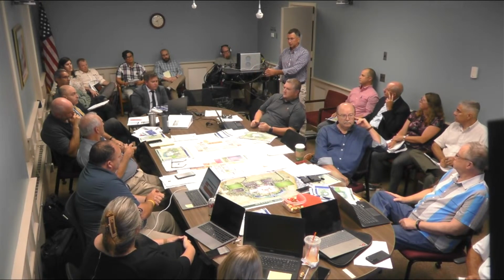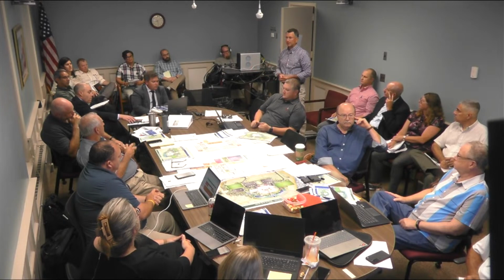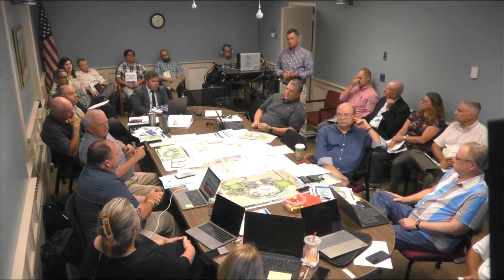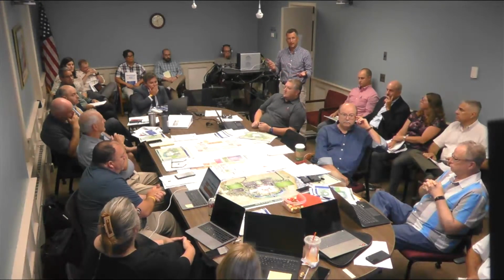It's typically much less. But we could go with a geo system and just design the space to later add in the PV. Yeah, we would design space in the switchgear for future addition of that. And that would be up to the school system at some point in the future, however they wanted to add that in. That's very common for a lot of municipalities to do. So you just build in the infrastructure for it. We put it in the switchgear so it's there, and all you're doing is putting your system on and plugging it in. So that's a long continuum of things we could do. You could go full PV, or just infrastructure, or nothing. That's correct. You have a lot of options.